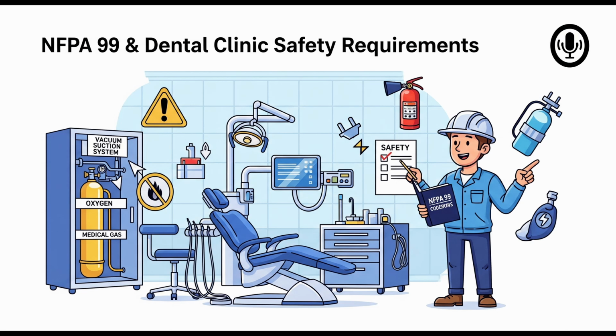Our mission today, then, is to pull out the key takeaways from the NFPA 99 text you've provided, specifically focusing on those engineering and safety requirements for dental clinics. Right. We'll look at mandatory systems, any space considerations, and try to pinpoint the specific sections that really apply. The goal is to make this dense code a bit more digestible for you, the listener, especially if you're navigating dental facility design or operations. And it's good to see, looking through the committee list in the source material, there was actually a representative from the American Dental Association on the technical committee for NFPA 99. Oh, that's interesting. Yeah, it suggests that dental considerations were definitely part of the conversation when this code was being developed. They weren't just an afterthought tacked onto hospital rules.